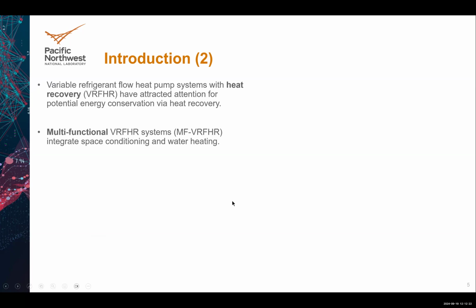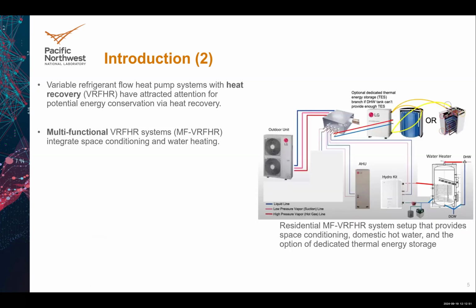When we talk about the integrated heat pump system, an example of the system is a variable refrigerant flow heat pump system with heat recovery. This kind of system has attracted attention for potential energy conservation via heat recovery. The VRFHR system that integrates space conditioning and water heating is also called a multifunctional VRFHR system, namely MF-VRFHR. So here is an example of the residential MF-VRFHR system setup that provides space conditioning, domestic hot water, and the option of dedicated thermal energy storage.